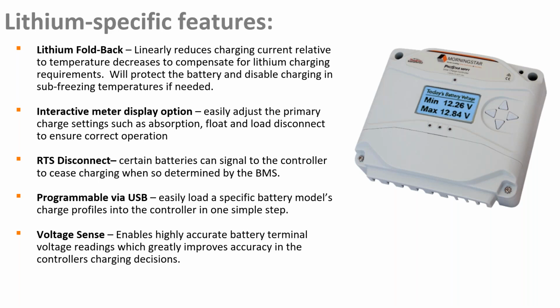For example, if your high temperature threshold is 10 degrees Celsius, and you shouldn't be delivering current to the battery below freezing, 0 degrees Celsius, that should be your low temperature cutoff. When you specify the high as 10 degrees and the low at 0 degrees, you get a linear derate of whatever the output current rating of the controller is, given adequate solar resource. It performs that linear derate of the output current into the battery. It's a very nice feature.